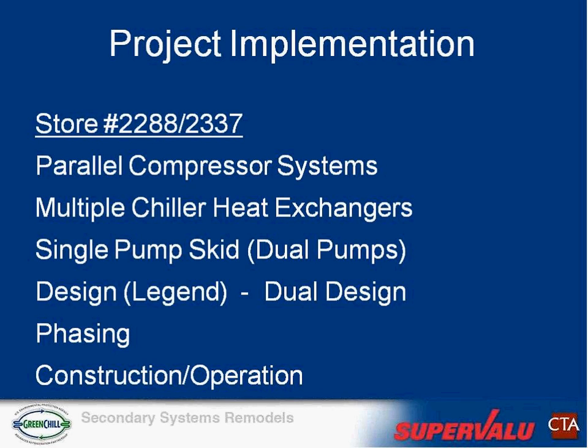So the next 2 projects were fairly similar. They were both shoppers projects on the East Coast, and we had parallel compressor systems there. We had multiple chiller heat exchangers, but again, it wasn't 1 per compressor, it was 1 per rack, and the pump setup was the same. Here we did something a little different because we wanted to identify costs a little more, and it'll show on the slide. We did it as if we weren't going secondary, as if this remodel was happening with the new cases we were getting and just what we've done with a typical design, leaving it all DX. Then we redesigned it in this application with a secondary design. That was just for bidding and equipment costs, but we really wanted to see what the cost difference was on bidding, and I'll get to that on the next slide.